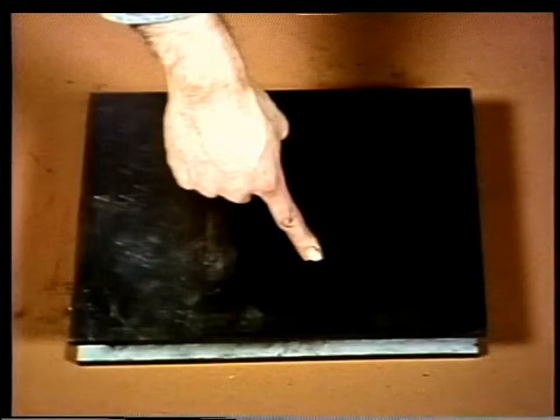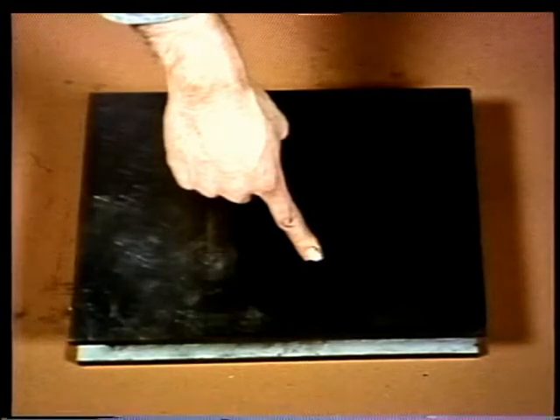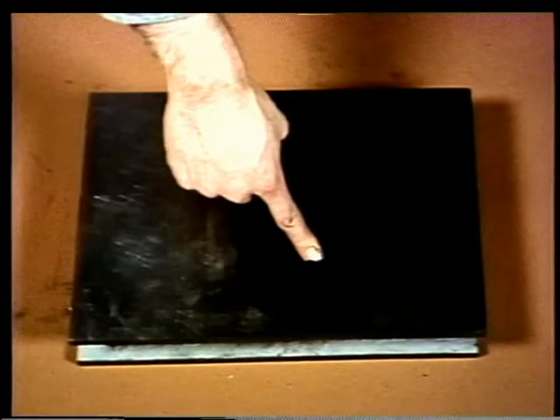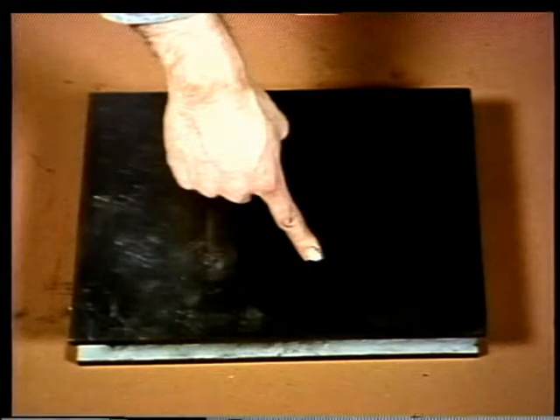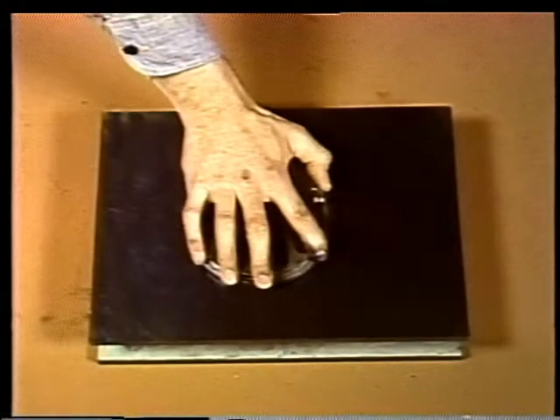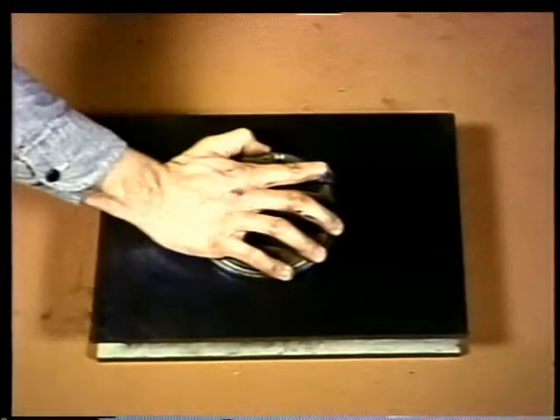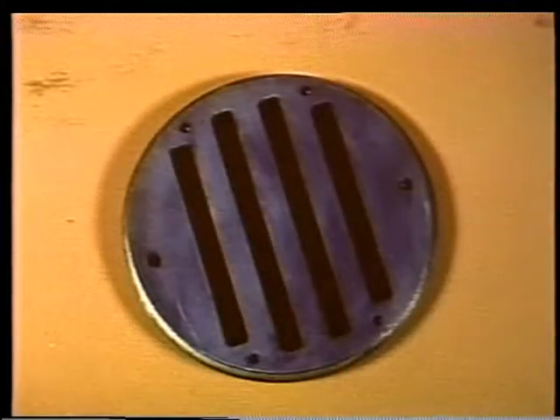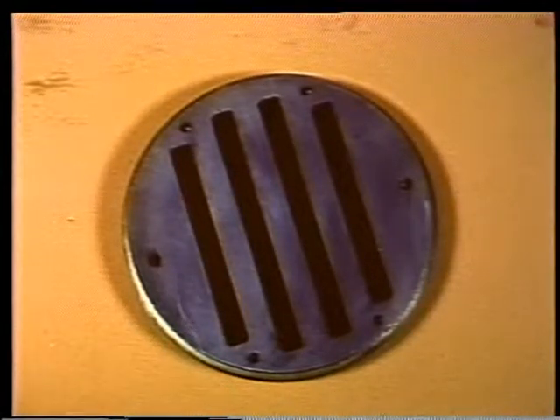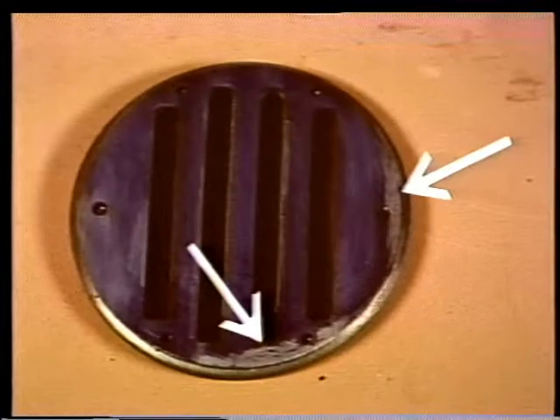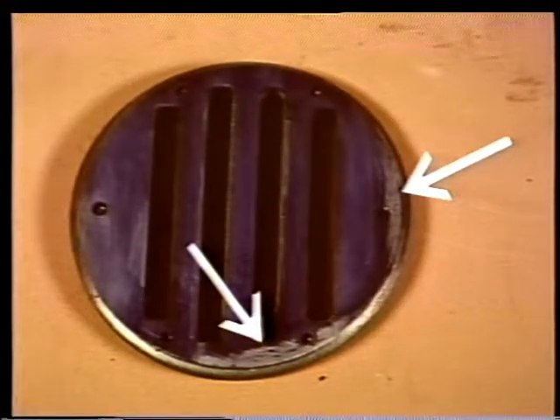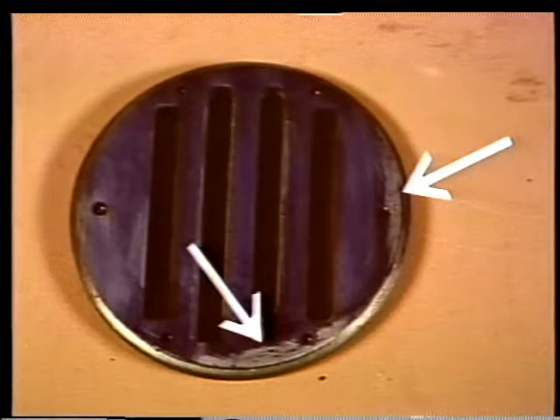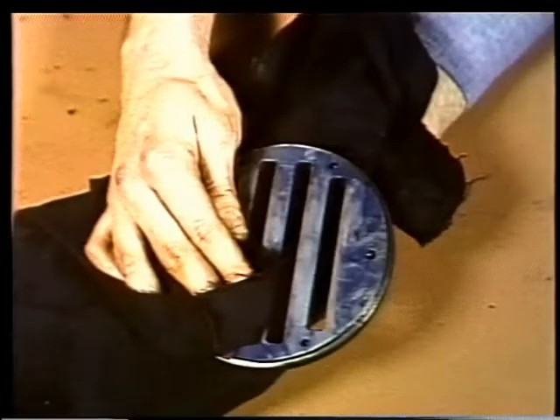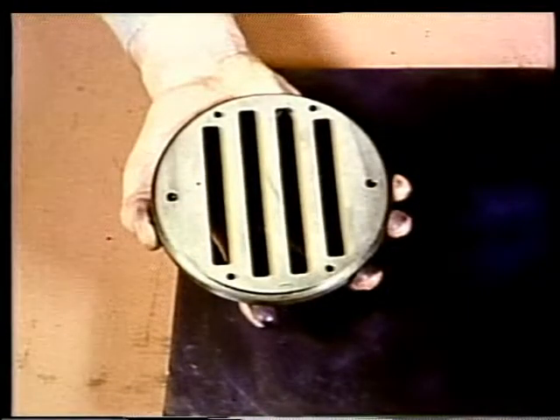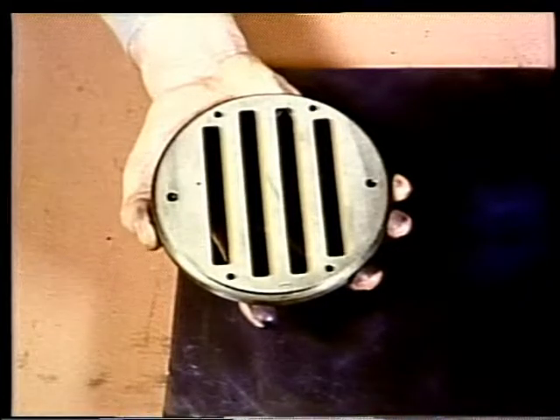Bluing is the process used to check the seating surface to be sure that there are no high or low spots. To do this, you apply a thin coat of bluing to a surface plate. Then place the valve seating surface down on the plate and turn it 1/4 turn. Remove the valve and check the seat. You should see a thin, even coat of bluing. Areas of uneven bluing indicate that the surface isn't flat yet, so it should be lapped and blued again until it's right. The next step is to thoroughly remove all traces of bluing. Once this is done, you know you have a good seating surface. Then you can start to put the valve back together.